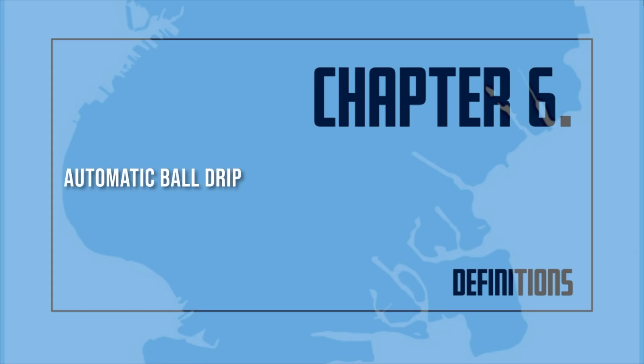Automatic ball drip. An automatic drain valve horizontally installed at the low point in the piping between the lower check valve and the fire department connection of an automatic sprinkler system. Water pressure from a fire department pumper automatically closes this valve. The valve automatically reopens when pressure ceases, permitting this piping to drain, thereby preventing freezing.